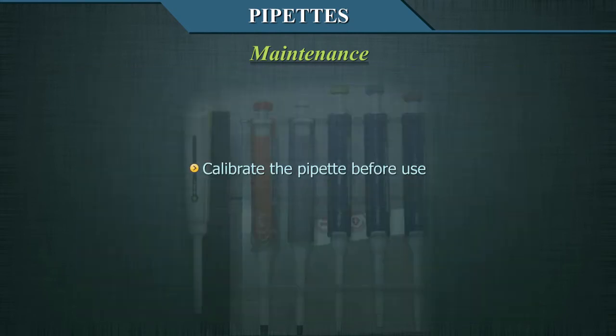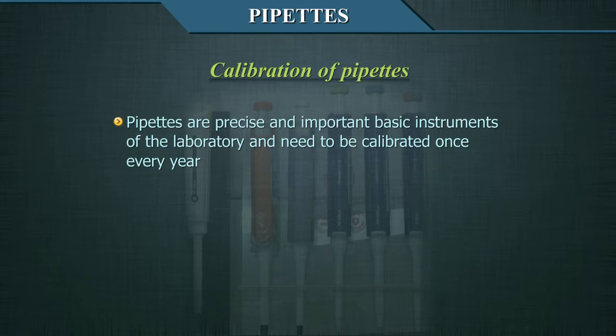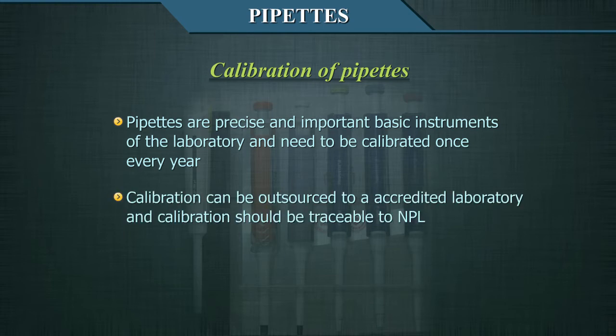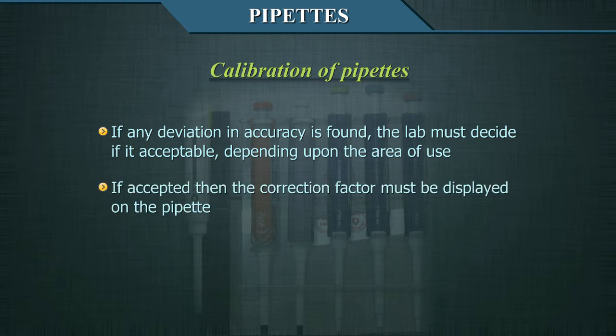Calibrate the pipette before use. Pipettes are precise and important basic instruments of the laboratory, and they need to be calibrated once every year. The calibration can be outsourced to an accredited laboratory, and calibration should be traceable to the NPL, the National Physical Laboratory. If any deviation in accuracy is found, the lab must decide if it is acceptable depending upon the area of use. If accepted, the correction factor must be displayed on the pipette.